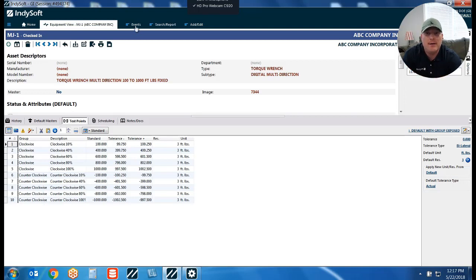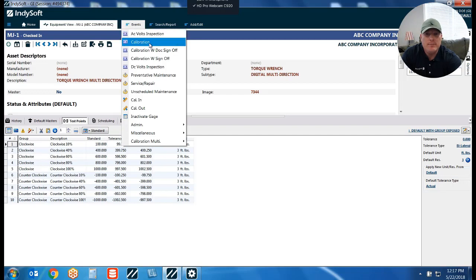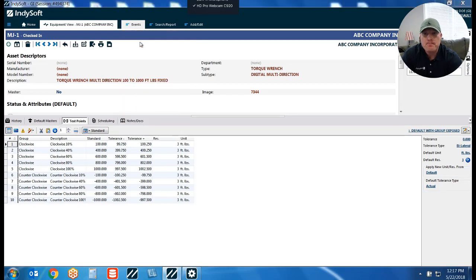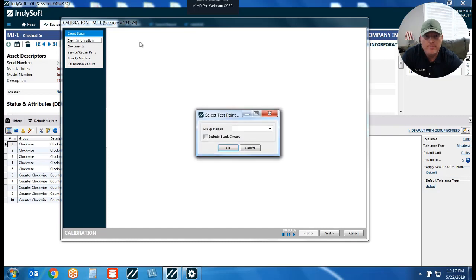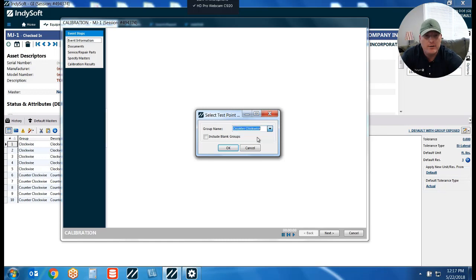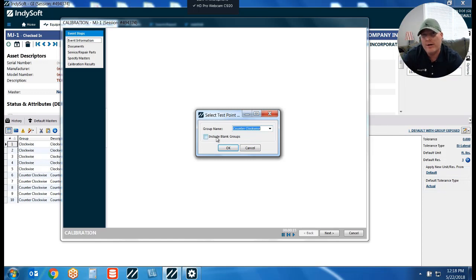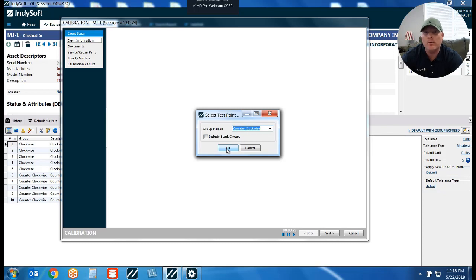Let me illustrate that concept. When I go to my events menu you'll see my calibration event. Once I launch that, we get a pop-up box asking which test point group we want to utilize. In my case, if I choose the counterclockwise measurements I just hit OK. I want to point out this checkbox that says 'include blank groups' — that would include any test points that did not have a group assigned if you checked that box. So here I'm choosing just my counterclockwise measurement points only.